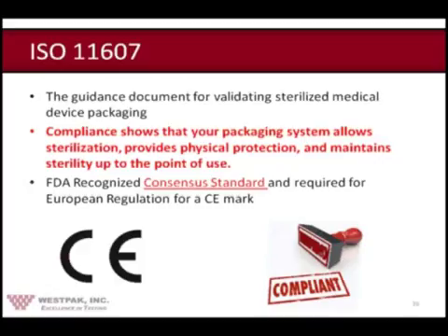Okay, let's move along. By this time I hope everyone has seen that accelerated aging is part of the standard, part of ISO 11607, and that it does trace its origin to the Arrhenius reaction rate for this accelerated aging of medical devices.